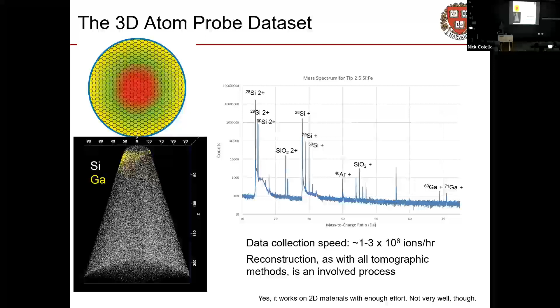So, materials this works really well for. Solids, don't bring me any gases. Things that don't mind being in UHV, which means they've got to be vacuum stable, they've got to tolerate various parts of the setup. Materials for which you're looking for absolute composition measurements, everything but oxides and III-Vs. We're not going to get absolute measurements on those, for reasons. But if you want relative composition measurements, meaning you think there's a difference between point A and point B, yes, those we can do even in oxides and III-Vs.